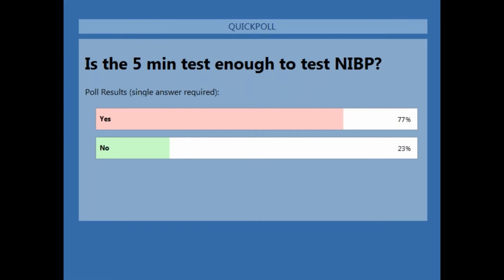So time is important to us, but the right amount of time should be spent to make sure everything is safe and effective for clinical use. So even if we took 15, our prior surveys that we've done worldwide now, not just with the United States, but worldwide, show us that if you follow the patient monitor manufacturer's test procedure, you may take 50, that's 50 minutes per patient monitor. If I can reduce that to 15 and still get all of the testing the manufacturer wants done, why would I not do that? Now I can really add more.